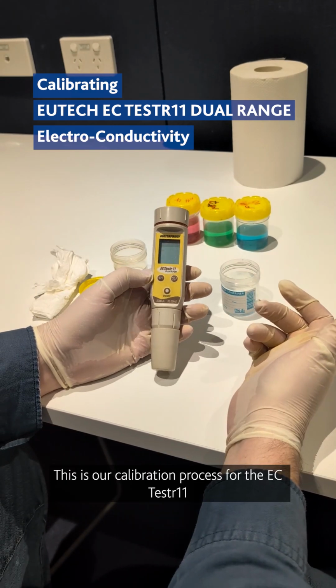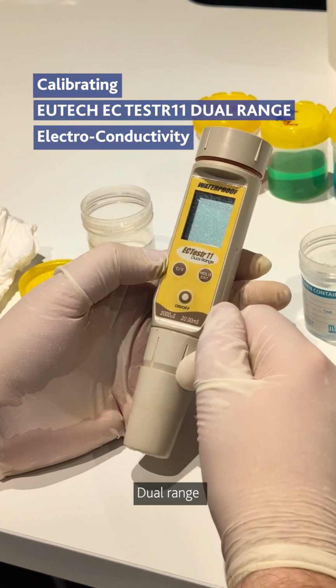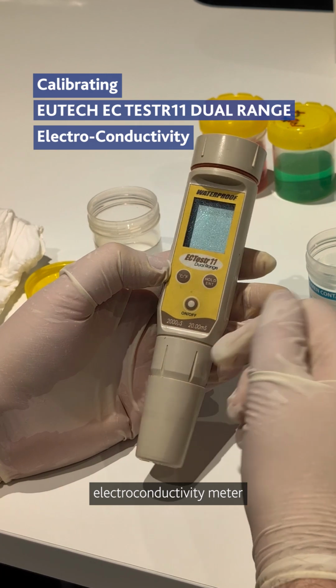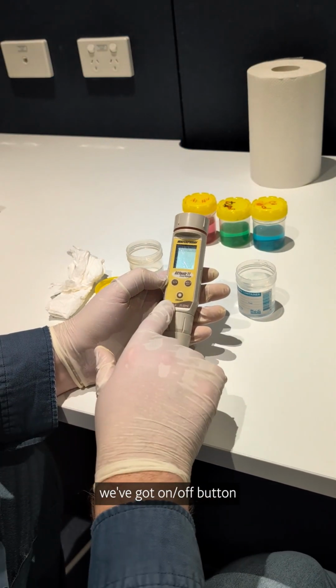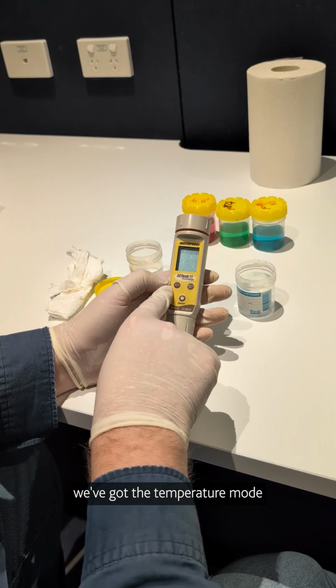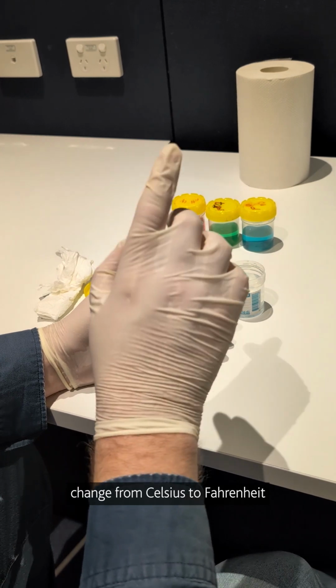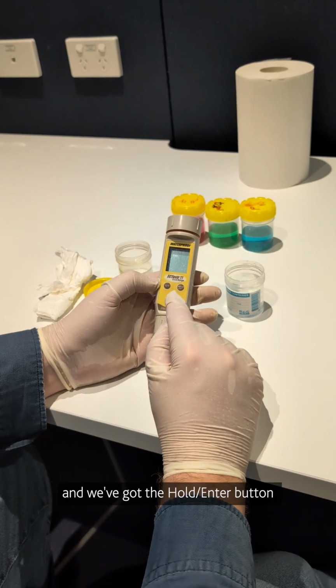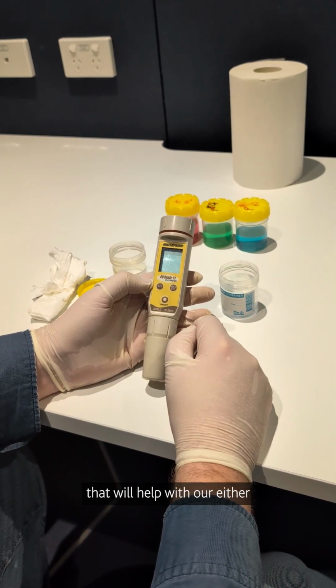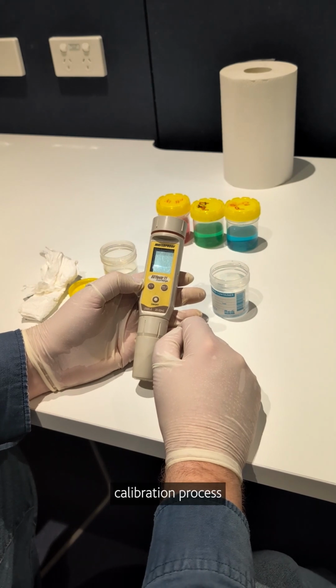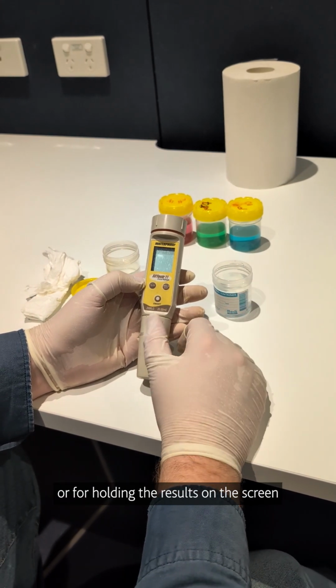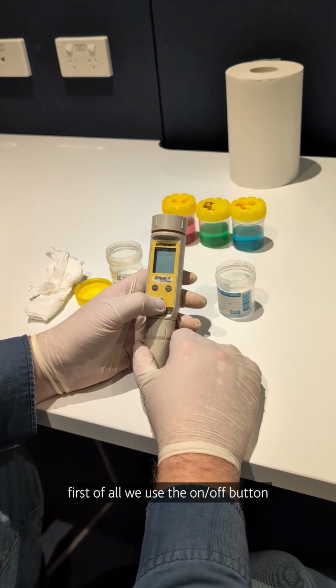This is our calibration process for the Testr11 dual range electro-conductivity meter. So with this unit, we've got three buttons. We've got the on and off button. We've got the temperature mode change from Celsius to Fahrenheit, but we leave it in Celsius for our records. And we've got the hold enter button that'll help with either our calibration process or for holding the results onto the screen. So first of all, we use the on off button.